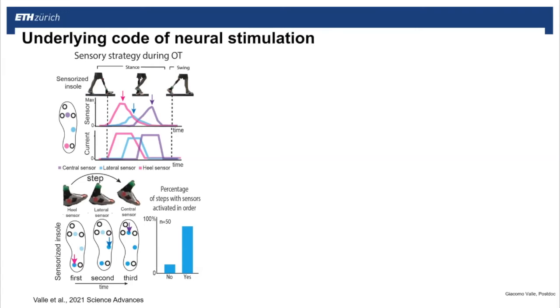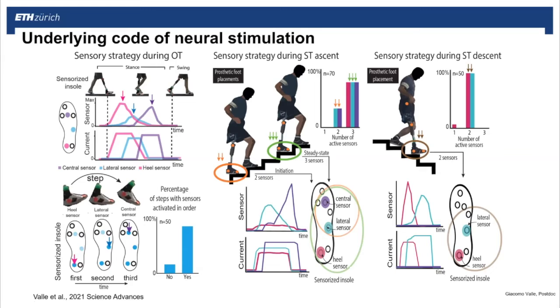And for example, we also observed on the stairs that the foot placement was different with sensory feedback and with no feedback, and the information about which sensor is activated is important for the patient to understand the correct placement on the stair. So, for example, when the patient ascends, so climbs the stair, it is important to place the entire foot, or at least two sensors activated, in order to transfer the weight of the patient to the prosthetic side in a secure way before stepping on the stair. And on the other side, in the descending phase, it is important to roll the foot and flex the knee. So the patient was using the information from the heel sensor and the lateral sensor to understand that the foot was placed in the correct way.